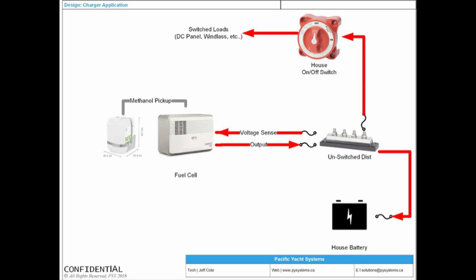If you buy a unit that says 210 on it, for instance, you're going to be outputting 210 amp hours a day. So that means over a 24-hour period, it's outputting about 8.4 amps every hour, continuously up to a maximum of about 210 amp hours a day. But notice what I did here, and this is very important because some people are buying these and installing themselves.